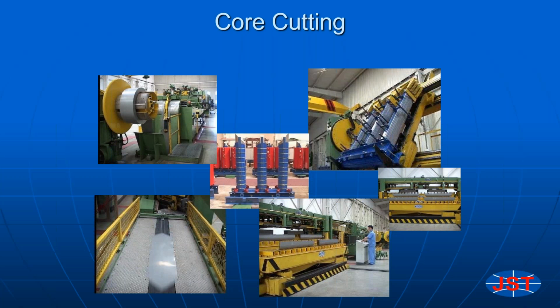And so eventually you build your core structure that's round in geometry and has the step lap mitered construction that you would need. And right in the middle here is a finished core ready for assembly, and the bottom's held together with what we call core clamps. These are stacking tables. As you can see in the background here are the multiple turrets. This is where they're stamped, and it's fed onto this stacking table that does everything automatically till you build your core logs.